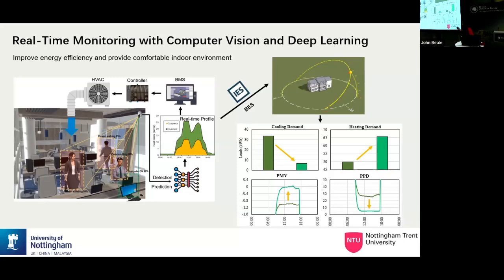As you can see in the results, compared to a typical static fixed schedule profile versus the deep learning-based profile, the cooling demand drops. At the same time, heating demand increases because we are providing a more comfortable indoor space — more heating in winter, especially in the UK. PMV and PPD are the indices to assess indoor comfort level. PMV increased toward zero, which is the optimal comfort level, and PPD decreased from around 25% to 5%, representing a significant improvement in indoor comfort.